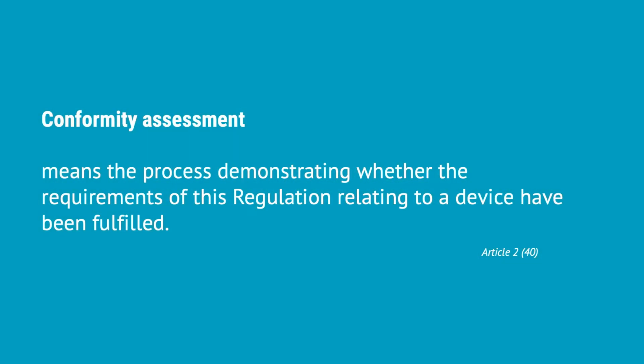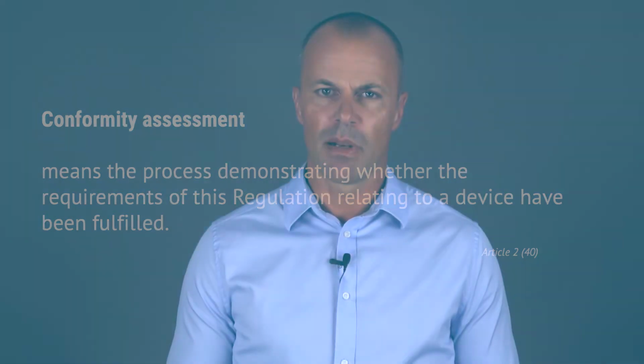So, back to the definitions. Conformity assessment means the process demonstrating whether the requirements of this regulation relating to a device have been fulfilled. But please note, this is not just the finished device that needs to be compliant. It is also the QMS that has governed the device to become what it is, unless you are following Annex 10 of MDR. And this is where the notified bodies come into the picture. I know this is a bit complicated, but I will explain further in the full course.